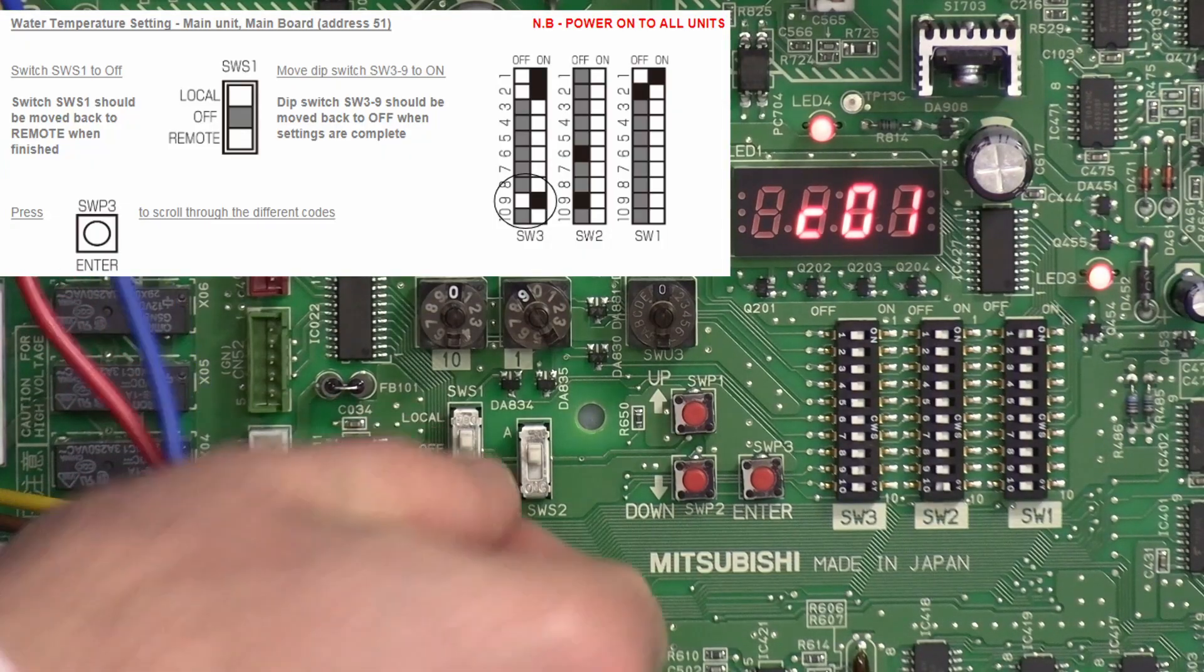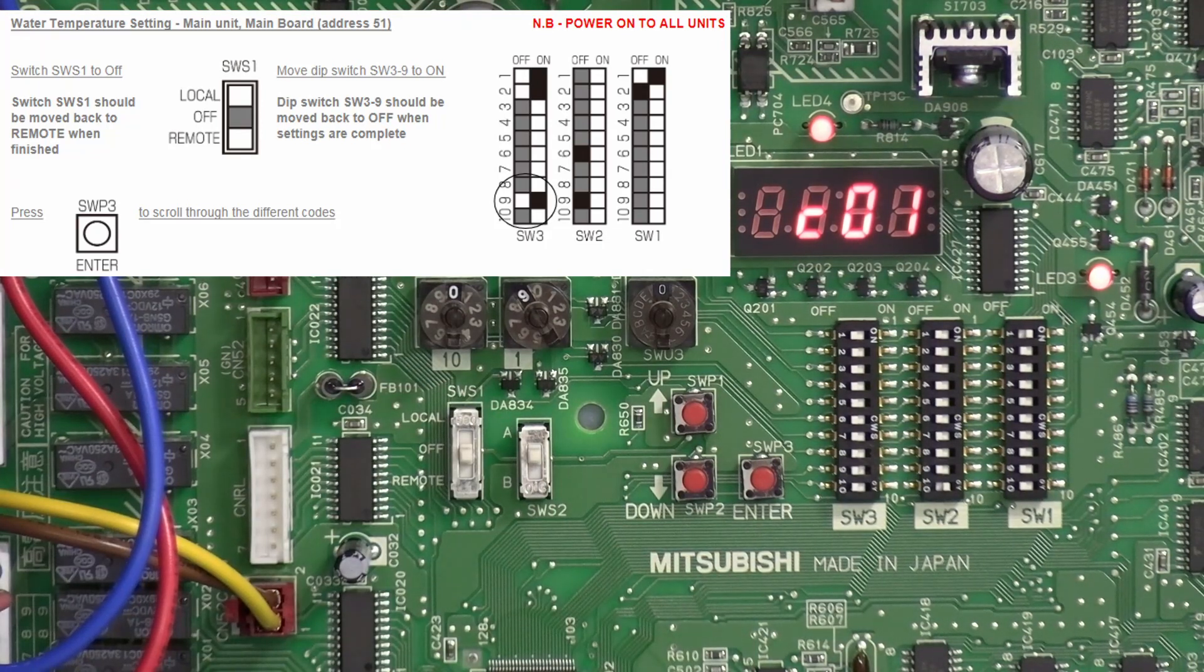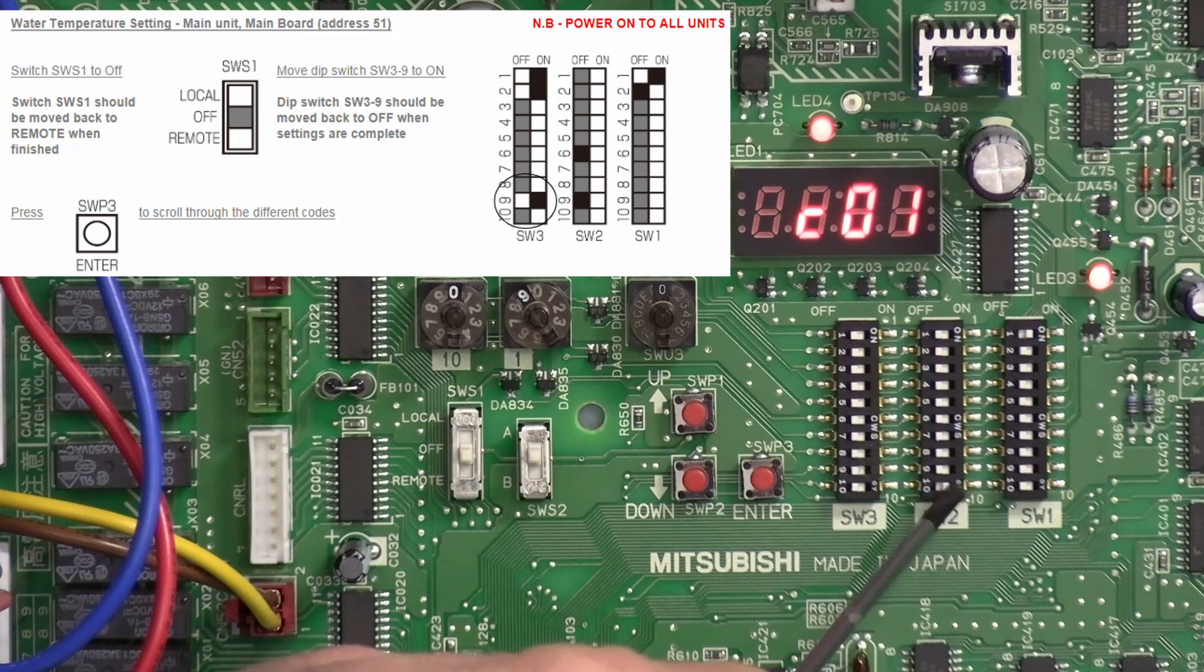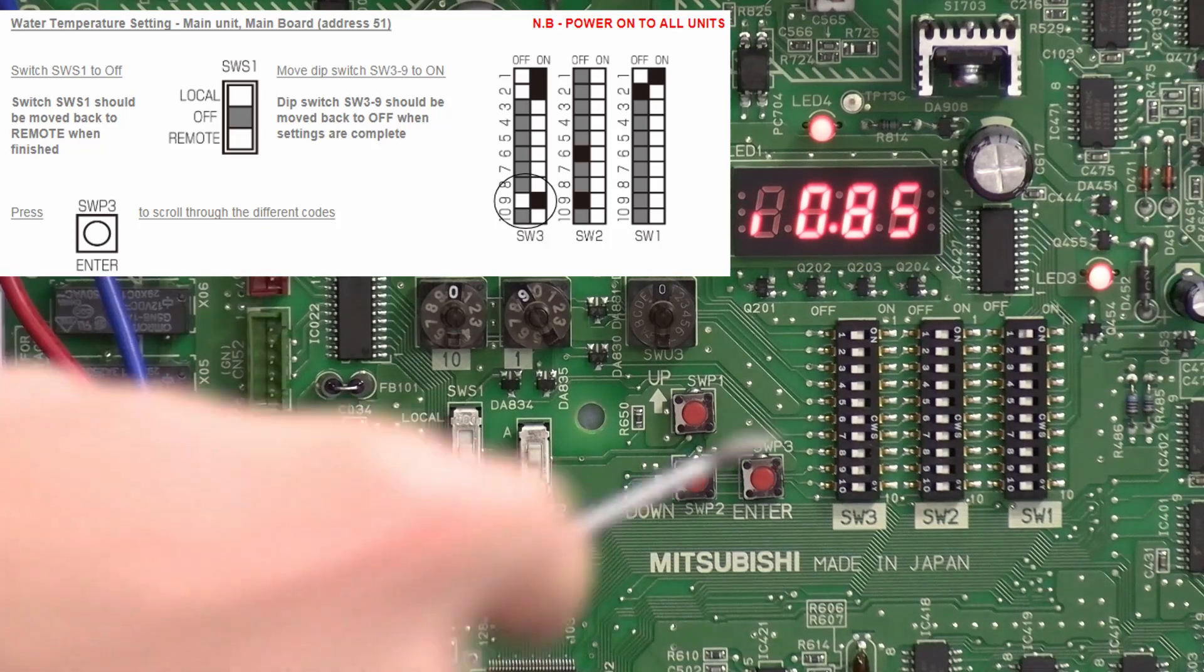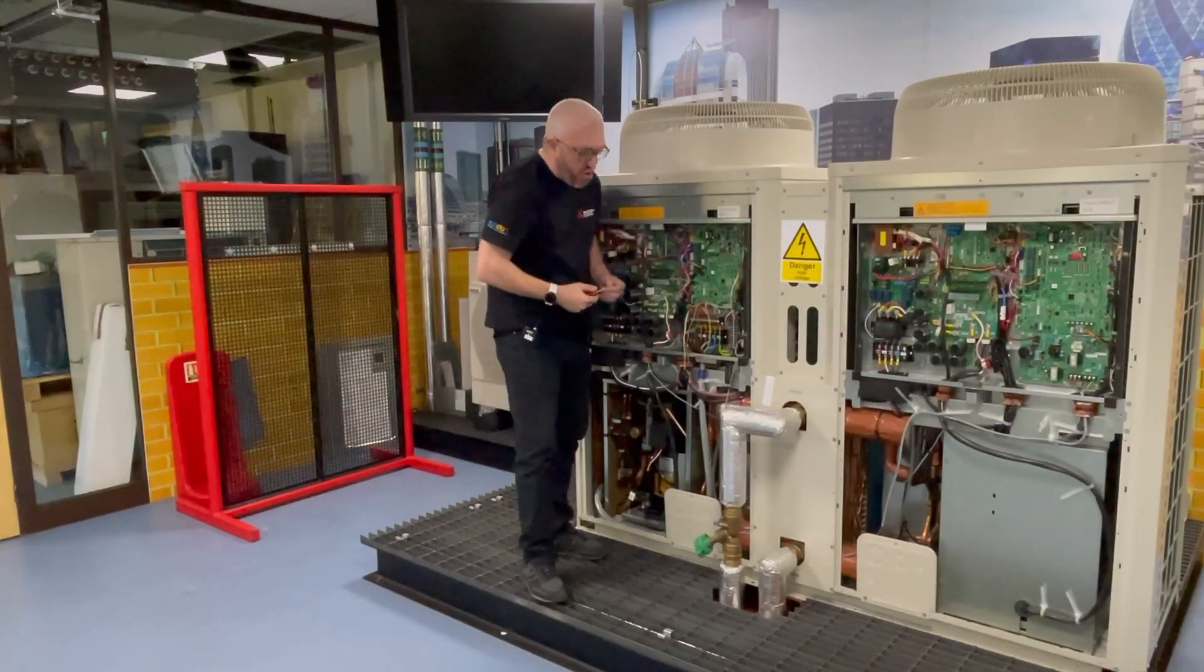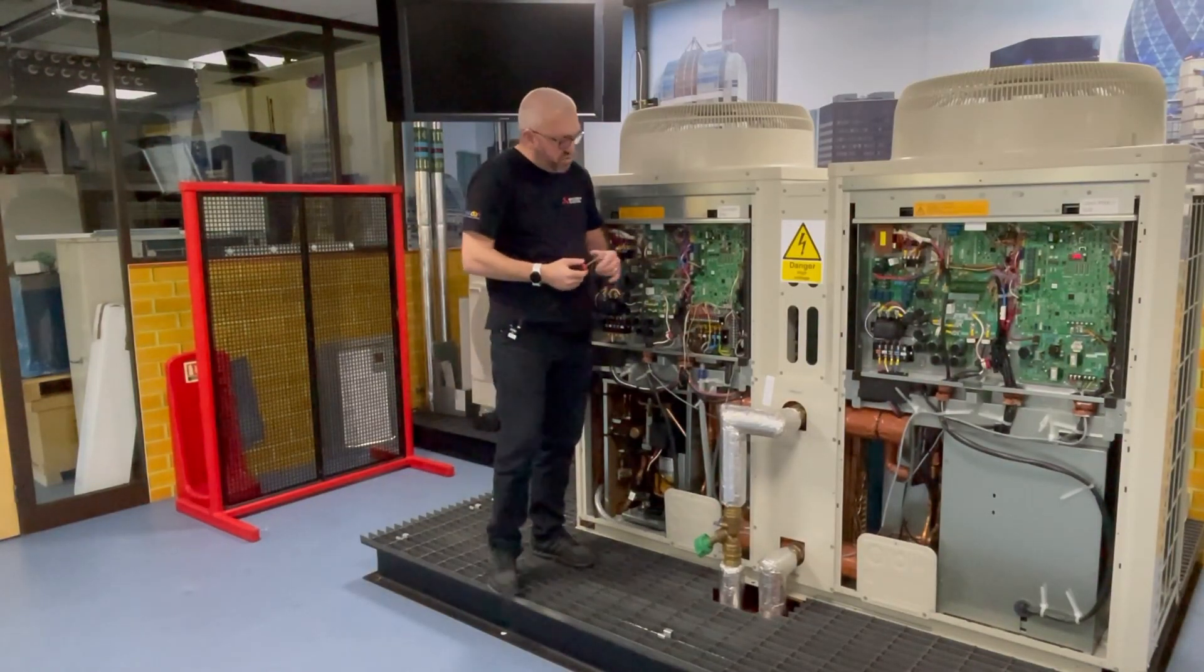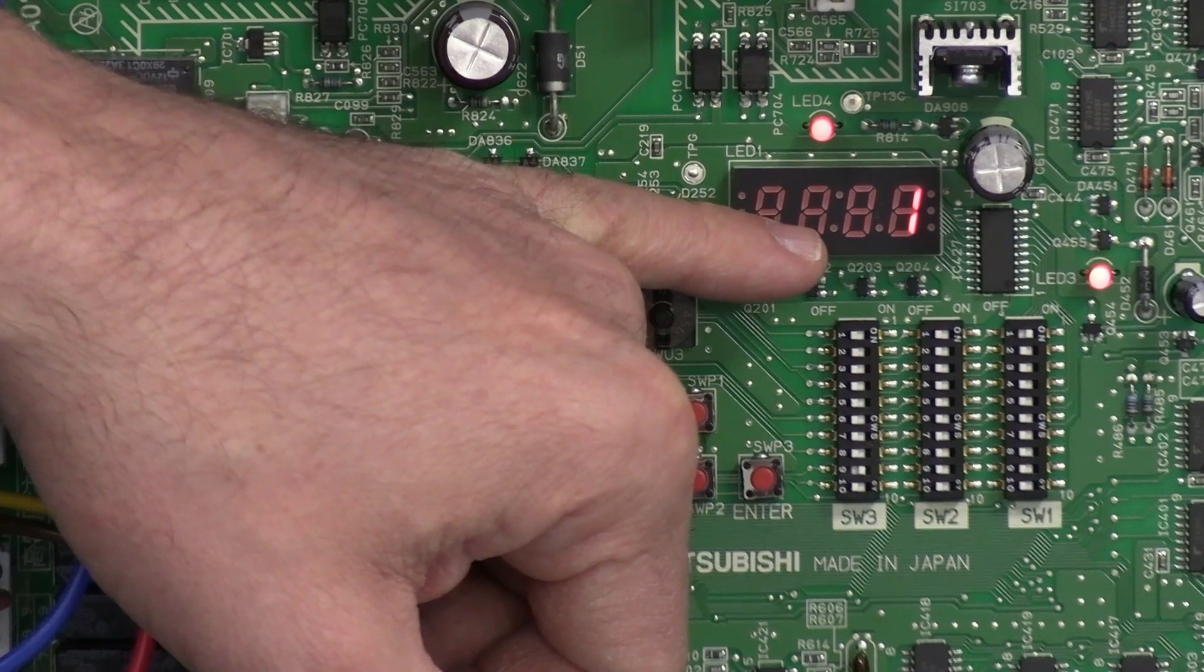First things first, we need to make sure that the SW S1 switch is in the off position, and then SW2 number 10 needs to be moved to the off position also. And then to enter into the setting we need to do SW3 dip switch number nine to the on position. You'll notice now that the LCD display has changed and we've got a number one there.